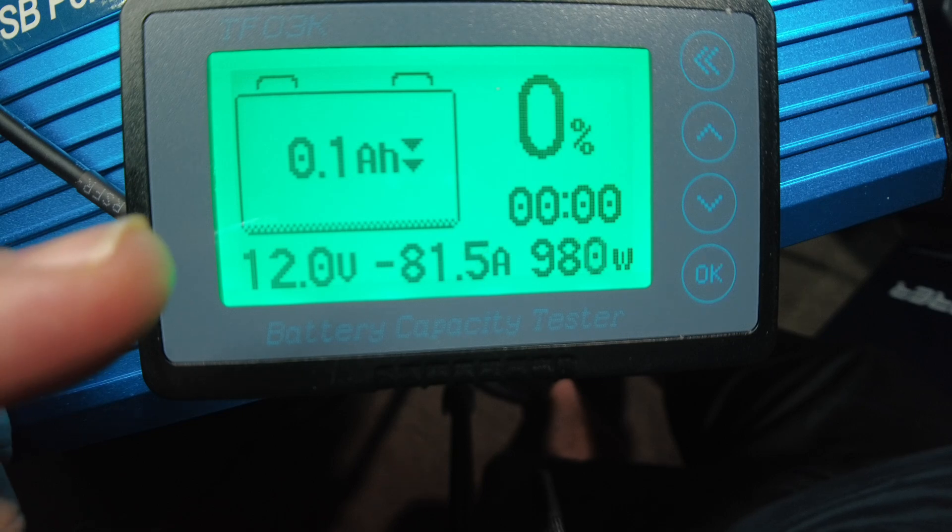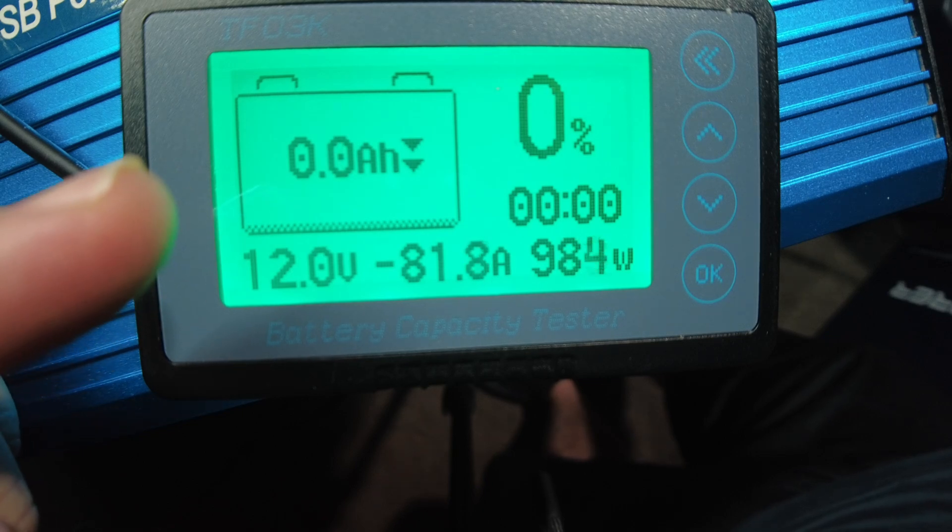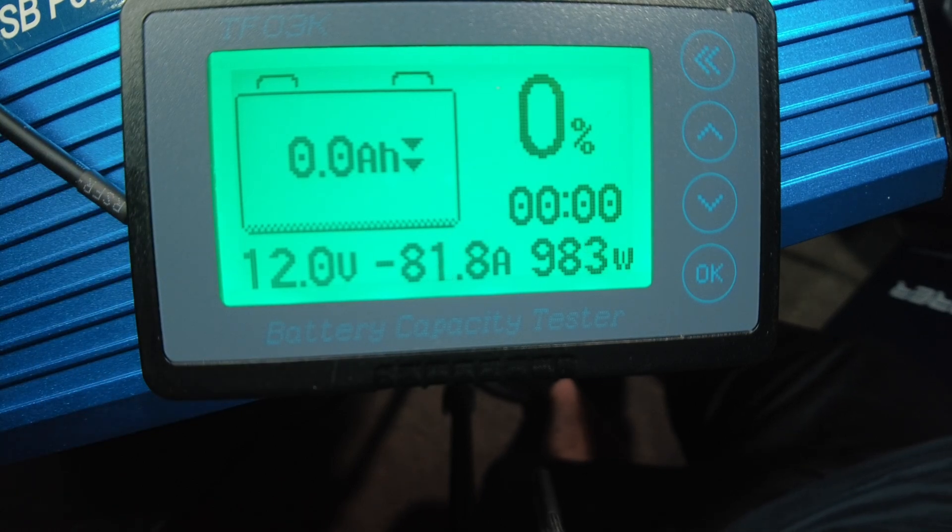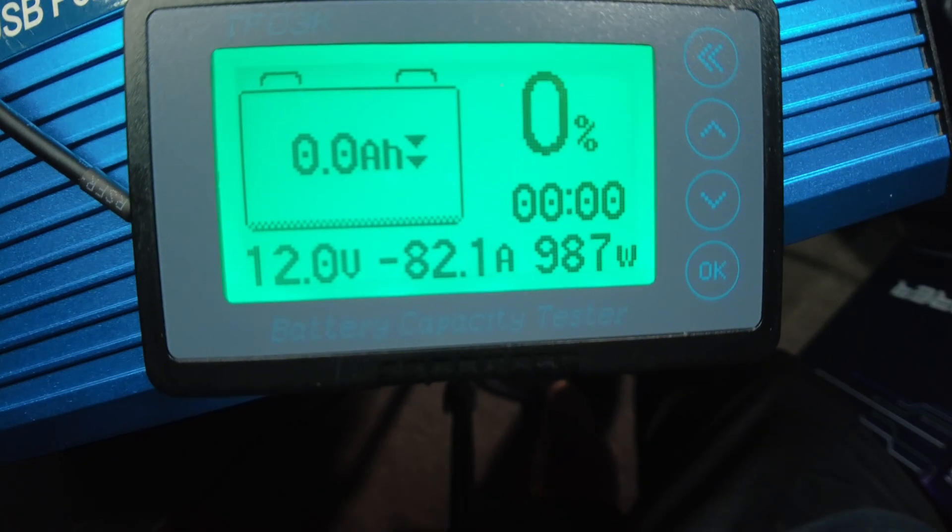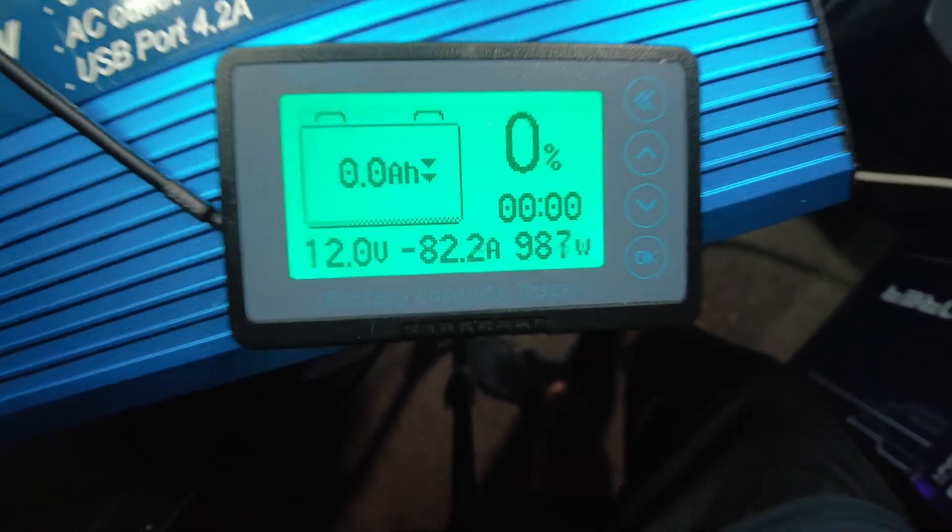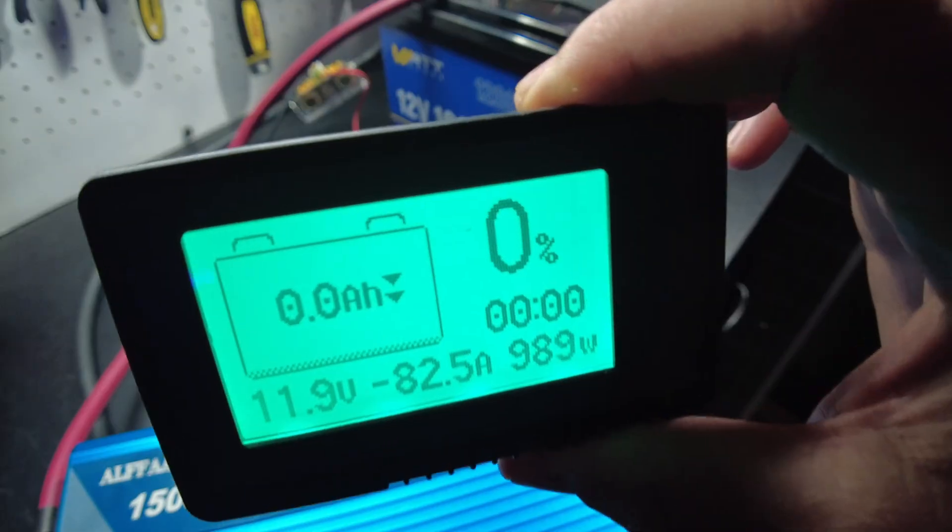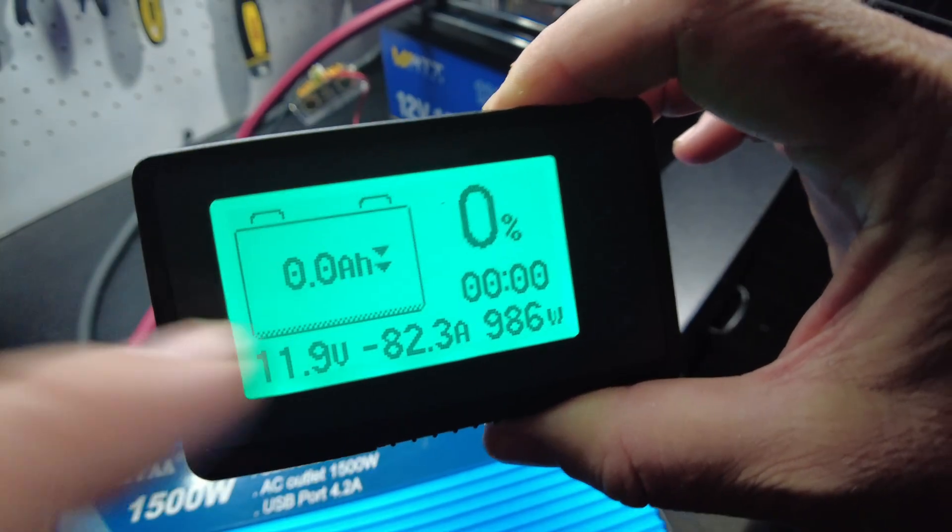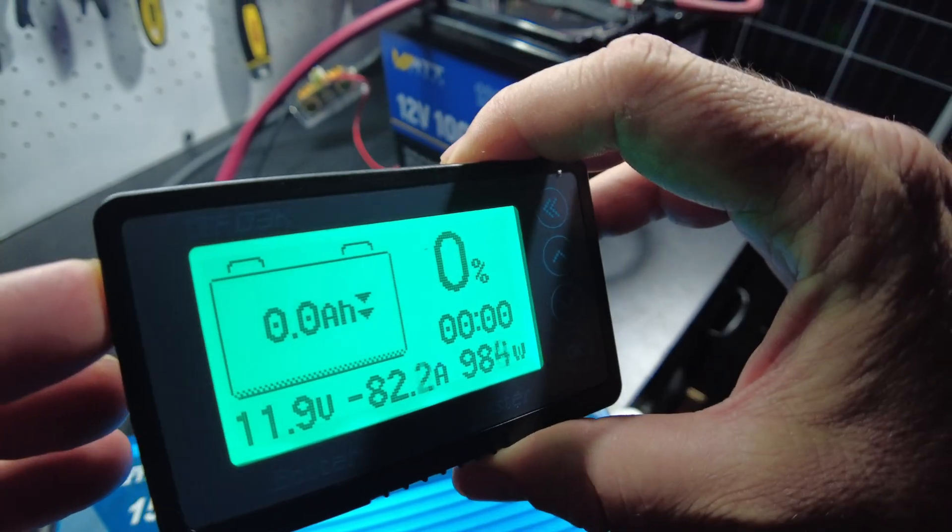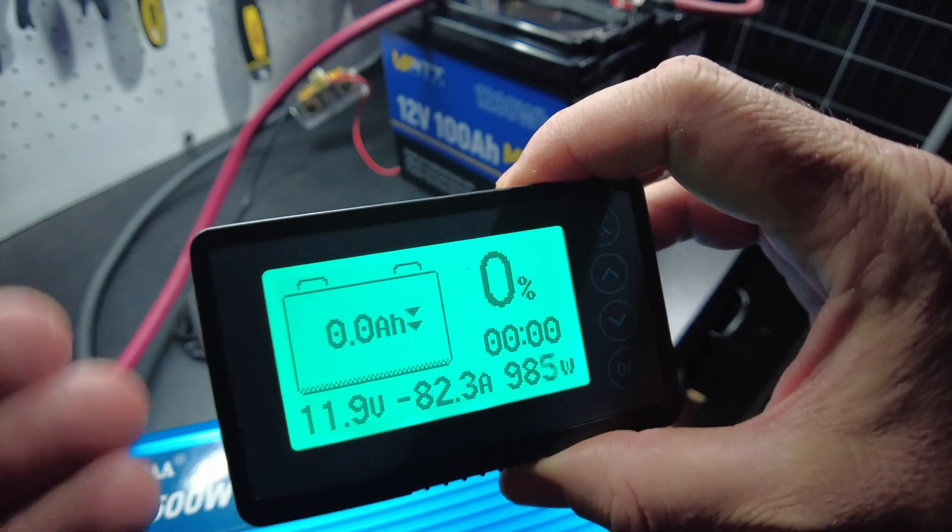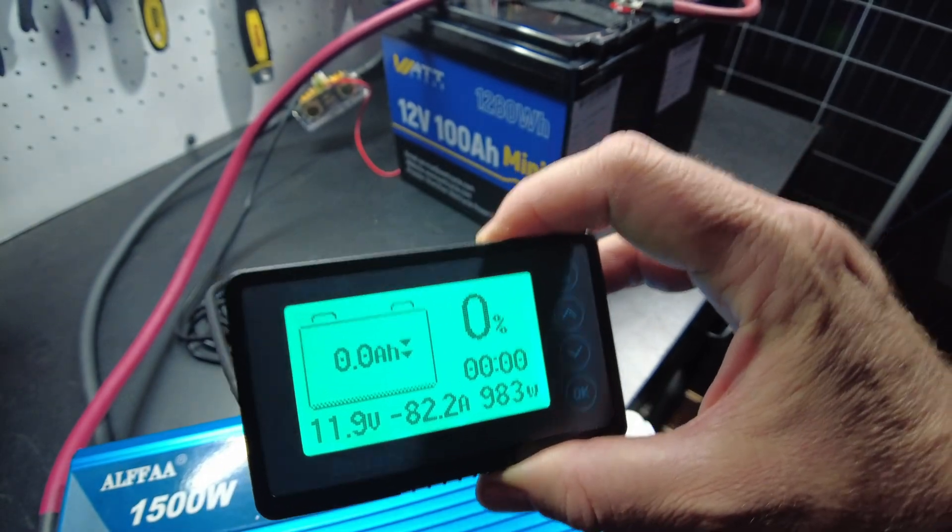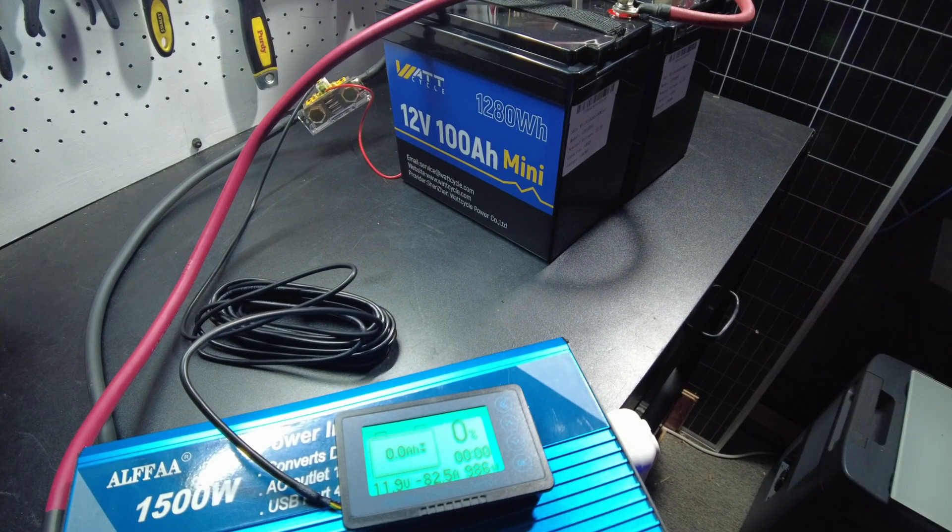Here we come. There we go. We've pulled a full 200 amp hours out of these two 100 amp hour batteries. And it's still going. I think I'm going to go ahead and turn it off because it's not actually going to tell us any more information. It's only going to tell us that we did in fact get 200 amp hours out of the batteries. So I'm going to go ahead and shut the test down.